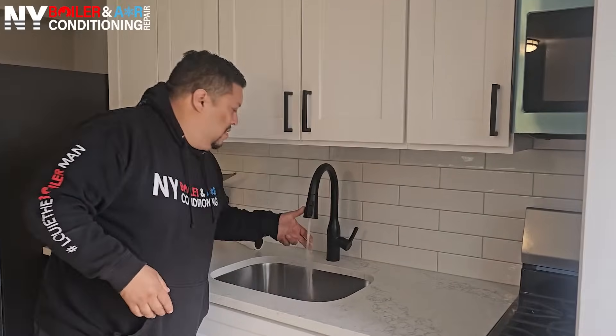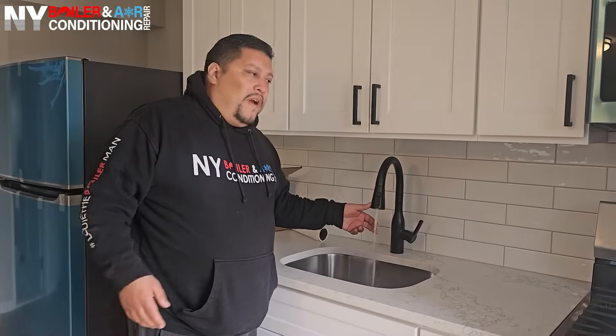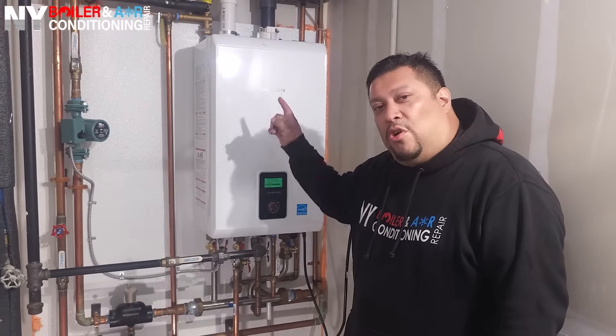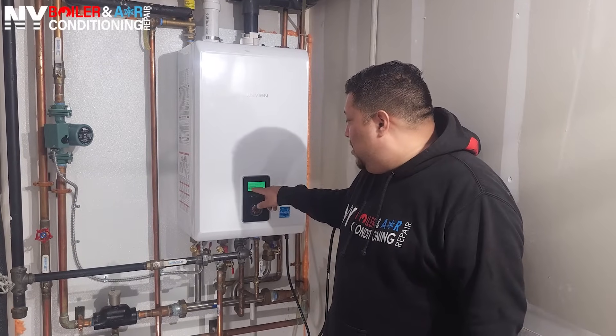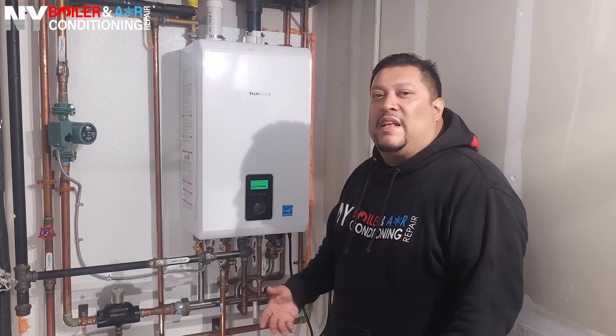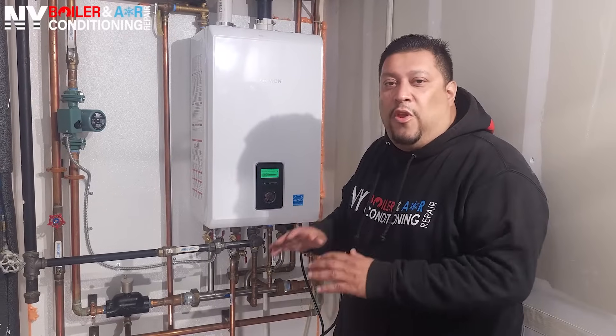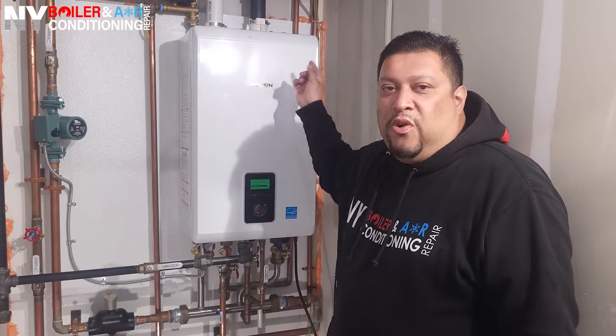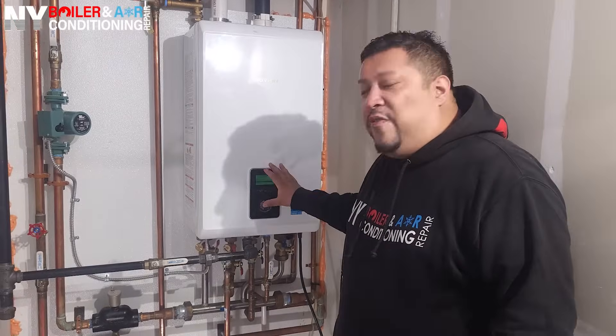We're in the apartment at the nearest fixture, about 15 to 20 feet away from the boiler. I'm going to open the faucet — the moment I do, that boiler should detect the flow of water and call for hot water. Now notice I have the faucet open. Back at the boiler room, DHW flow still reads 0.0 gallons per minute. That tells me right away we have an issue with flow — the boiler is not recognizing the flow of water even though we can physically open the faucet.